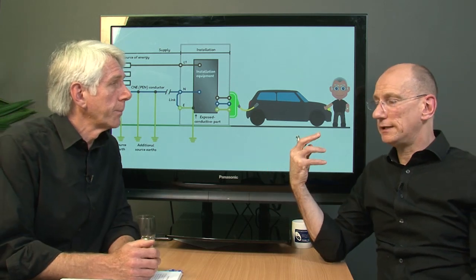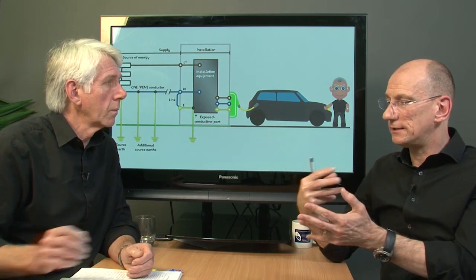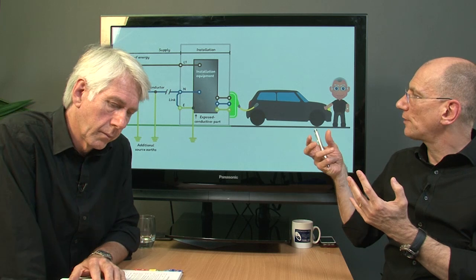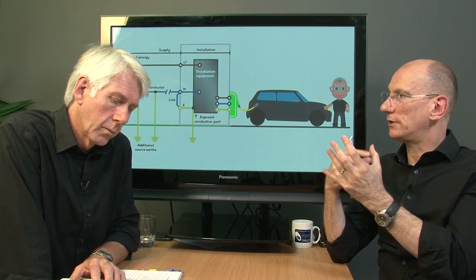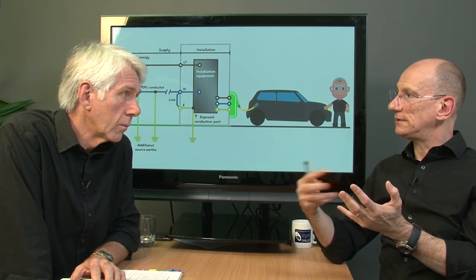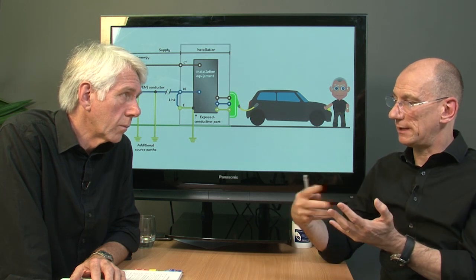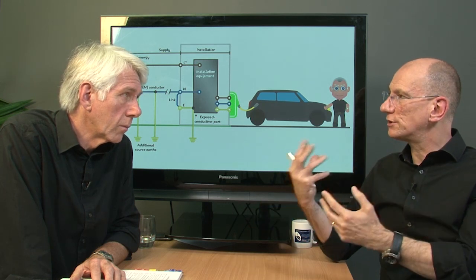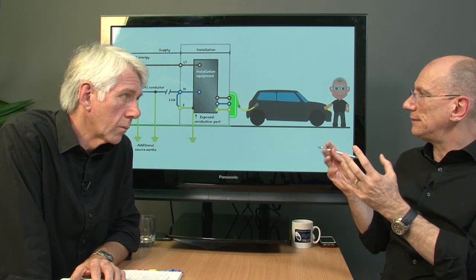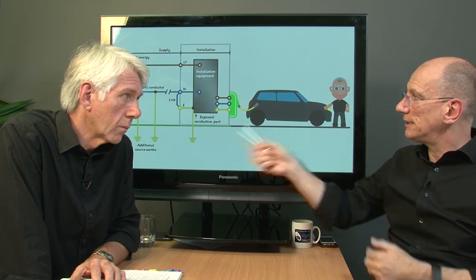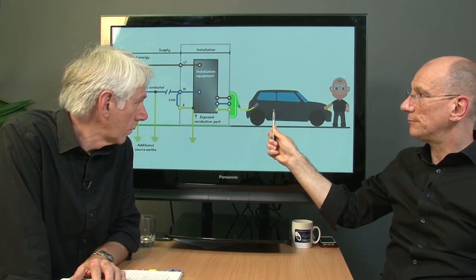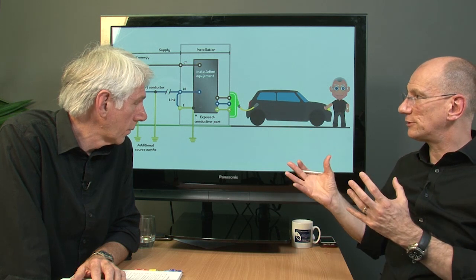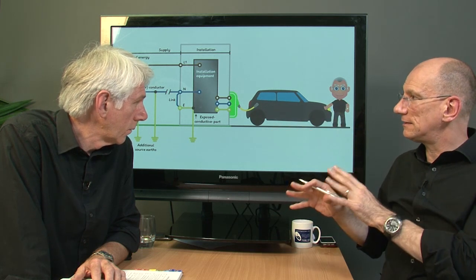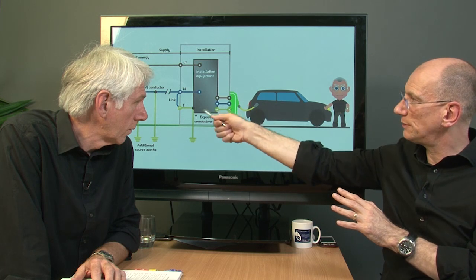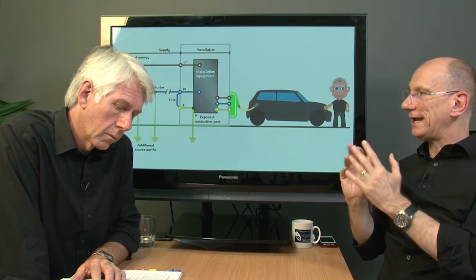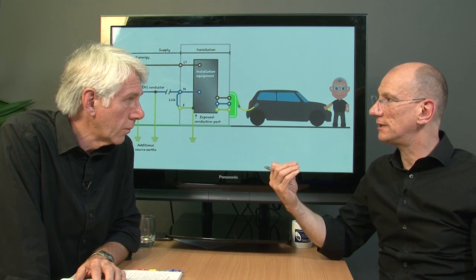There's a bit more detail we could tease out there. This particular device never existed in the 17th edition - I think it was Amendment 2 when it came out. It was looking to monitor the neutral, and even if you had an RCD and it tripped, the protective conductor is still in contact with the outside metalwork. So even if it disconnected the line or neutral and there was a rise in potential, it would probably still export out. So it needs to disconnect the protective conductor at the same time.